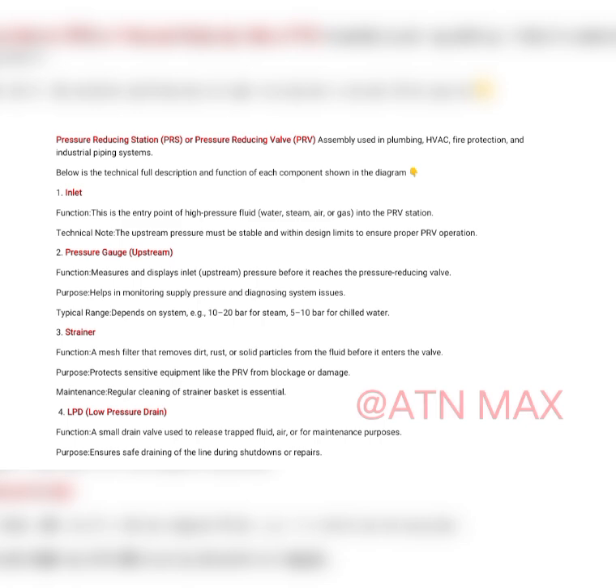Technical note: the upstream pressure must be stable and within design limits to ensure proper PRV operation. 2. Pressure gauge, upstream. Function: measures and displays inlet, upstream, pressure before it reaches the pressure-reducing valve. Purpose: helps in monitoring supply pressure and diagnosing system issues. Typical range: depends on system, e.g., 10 to 20 bar for steam, 5 to 10 bar for chilled water.